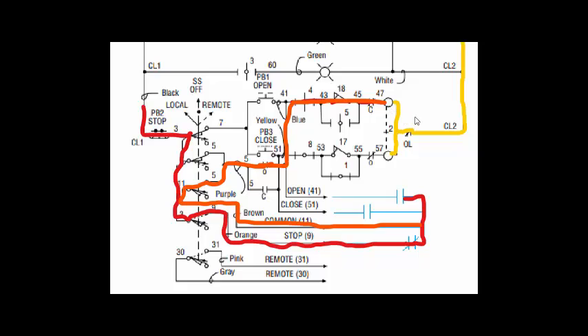And then the motor will not start again until we press the start button. Because once for example an overload trips, no neutral, there's no voltage going across it. If there's no voltage going across that coil, this contact here is going to open even when this gets reset.